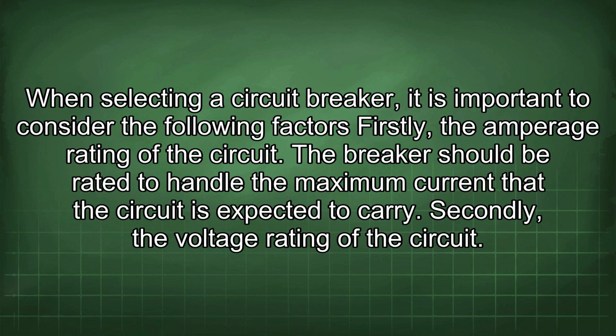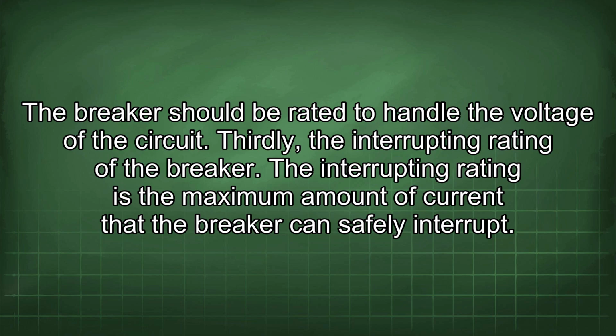Firstly, the amperage rating of the circuit. The breaker should be rated to handle the maximum current that the circuit is expected to carry. Secondly, the voltage rating of the circuit. The breaker should be rated to handle the voltage of the circuit. Thirdly, the interrupting rating of the breaker. The interrupting rating is the maximum amount of current that the breaker can safely interrupt.